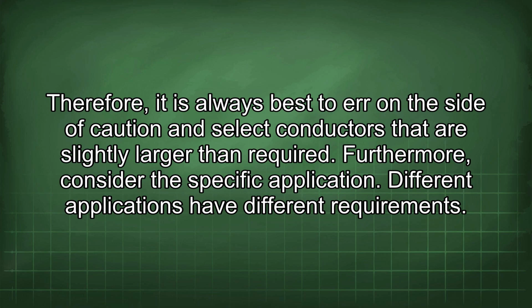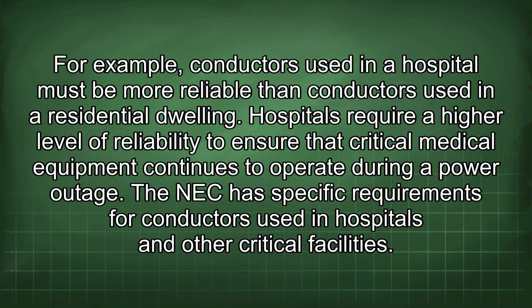required. Furthermore, consider the specific application. Different applications have different requirements. For example, conductors used in a hospital must be more reliable than conductors used in a residential dwelling. Hospitals require a higher level of reliability to ensure that critical medical equipment continues to operate during a power outage. The NEC has specific requirements for conductors used in hospitals and other critical facilities.